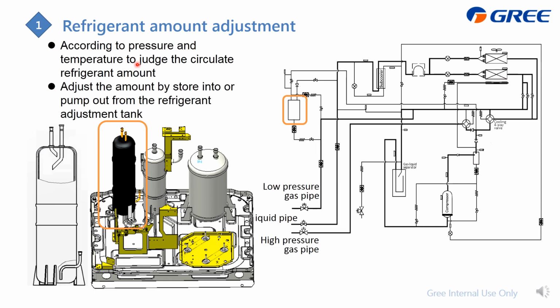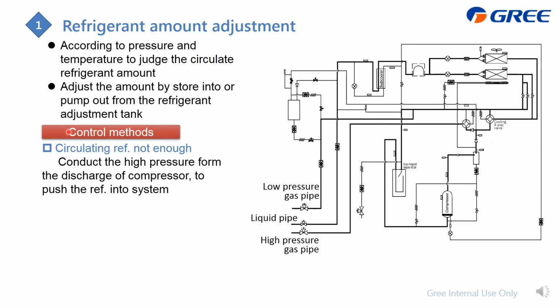If it is not, we have an adjusting method: the refrigerant is stored into here, or by the pressure we pump the refrigerant out from there to adjust the circulated refrigerant amount. Here is the detailed control method. If we detect the circulating refrigerant is not enough, we will conduct the high pressure from the compressor discharge, which is from here, to here, and then make this refrigerant out.